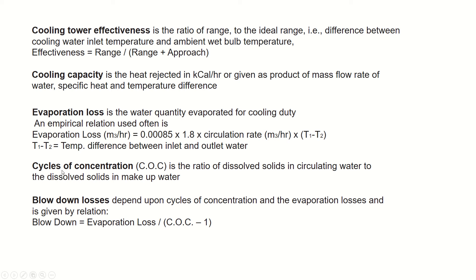Cycles of concentration is the ratio of dissolved solids in circulating water to dissolved solids in the makeup water. The circulating water between the cooling tower and the power plant heat exchangers gets a higher concentration of TDS compared to fresh water, so it is the ratio between TDS of circulating water and fresh water.